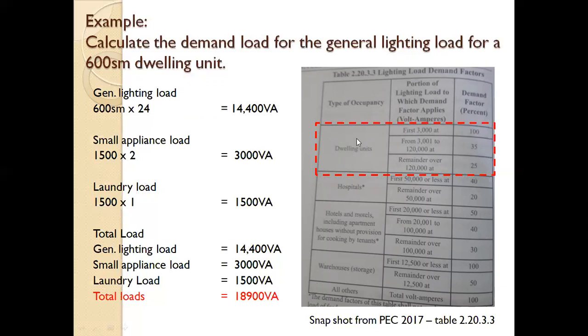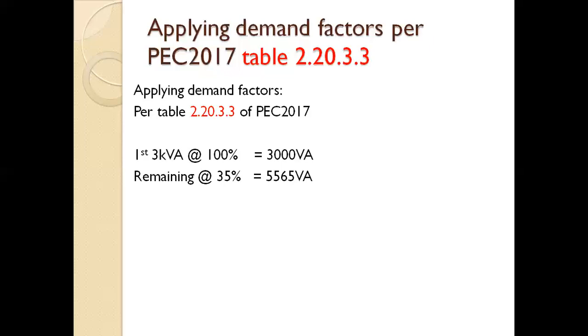In Table 2.20.3.3, this is the application of demand factors. For dwelling units, the first 3 kVA is at 100% demand factor, then the remaining is 35%. How is this applied? Let's look at the next slides. Applying demand factors per PEC 2017 Table 2.20.3.3, for the load of 18.9 kVA earlier, the first 3 kVA is at 100%, so we have 3 kVA. For the remaining, 18.9 kVA minus 3 kVA, you take 35%.